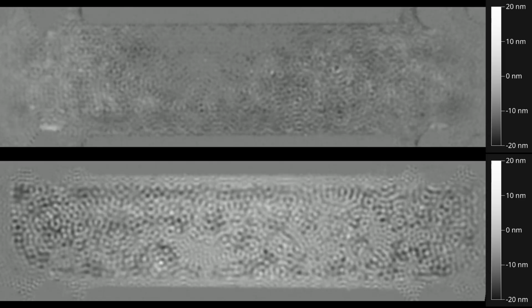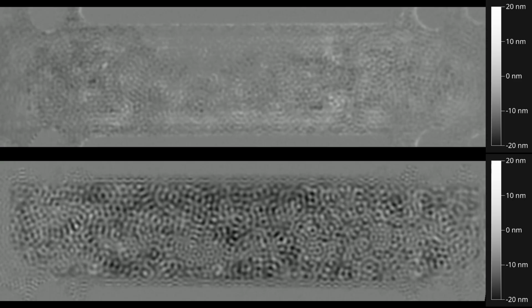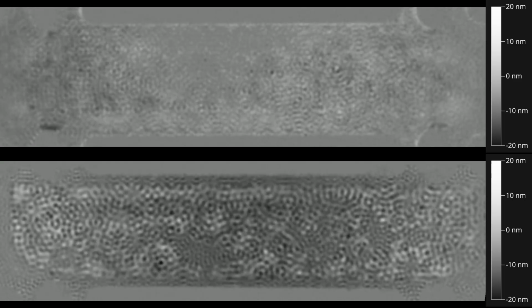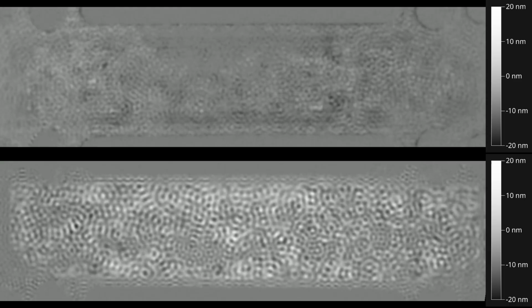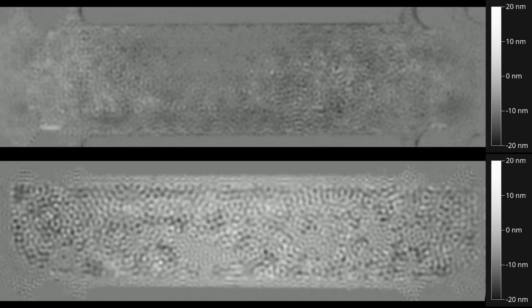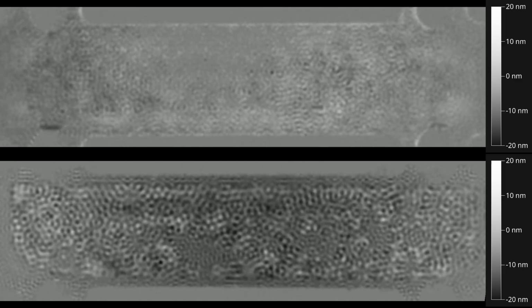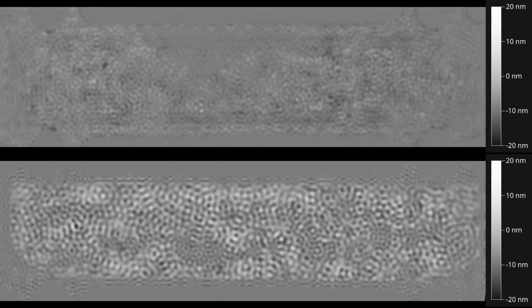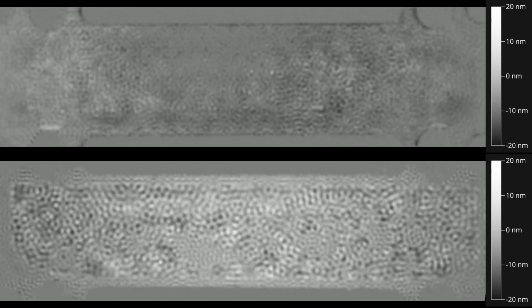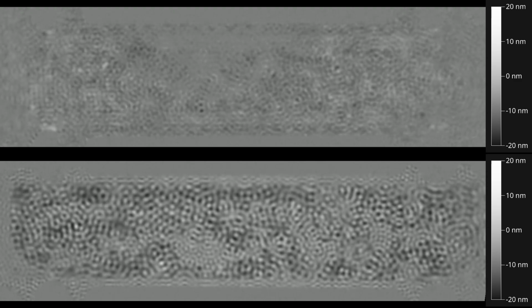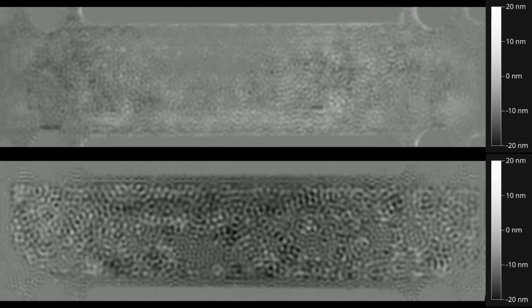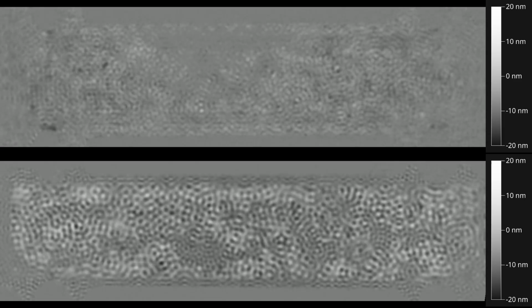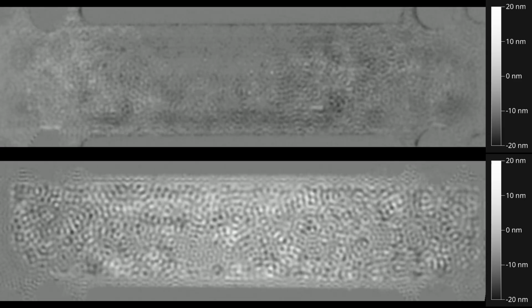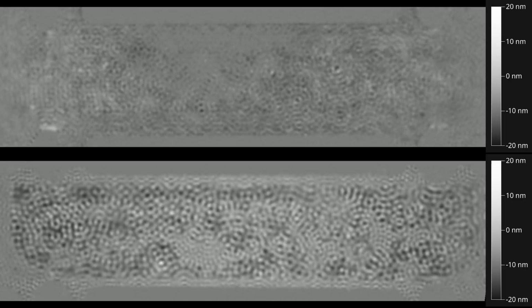At 3.2 MHz, we see that the newer sample moves like a piston, as it should. But the older sample has a very different and much less efficient behavior. It seems to have a more sinusoidal movement across the length of the transducer. Here we see that we also pick up minor details on the surface of the transducer, but these are apparently not related to the overall movement of the transducer itself. They are possibly related to bulk waves associated with small-scale structures somewhere inside the transducer. Though as we don't really know how the transducer is produced, this is only a hypothesis.